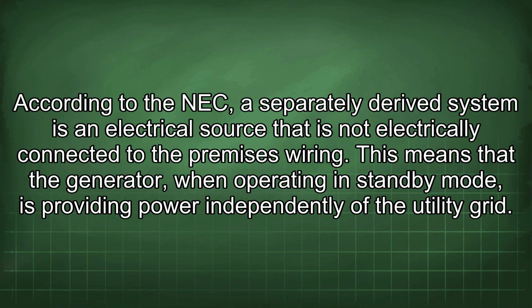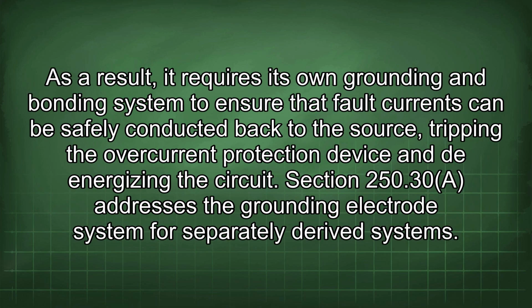This means that the generator, when operating in standby mode, is providing power independently of the utility grid. As a result, it requires its own grounding and bonding system to ensure that fault currents can be safely conducted back to the source, tripping the overcurrent protection device and de-energizing the circuit.